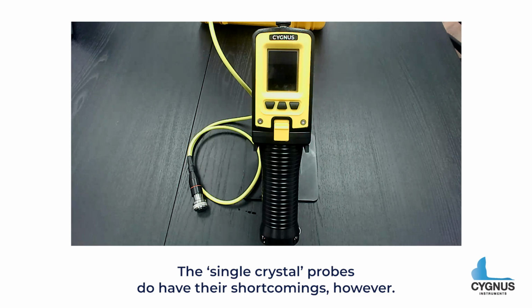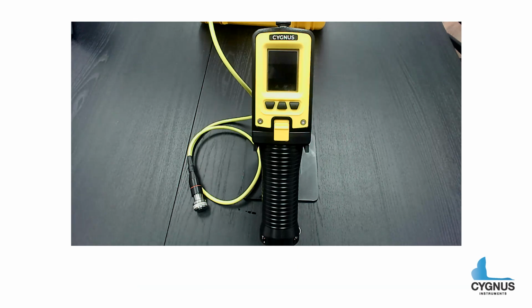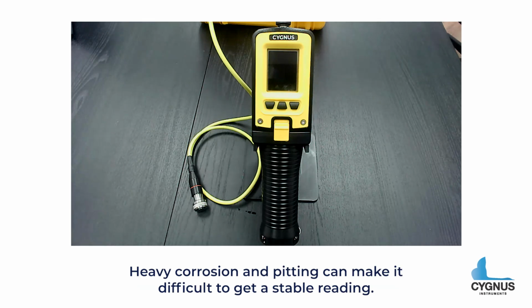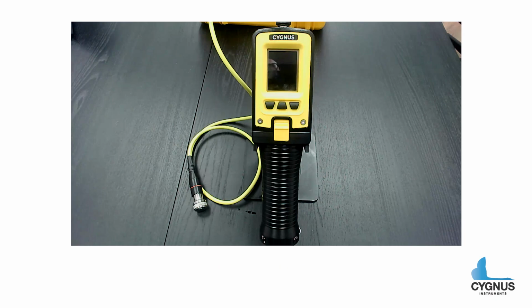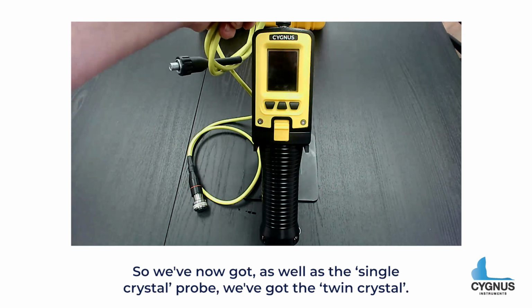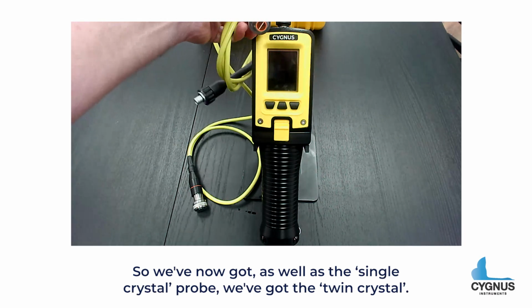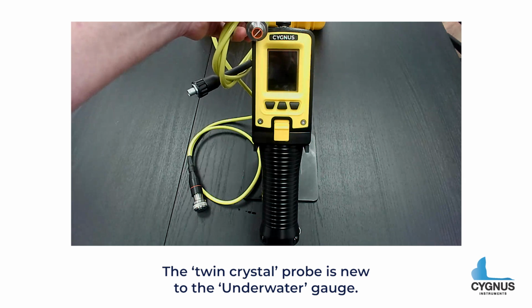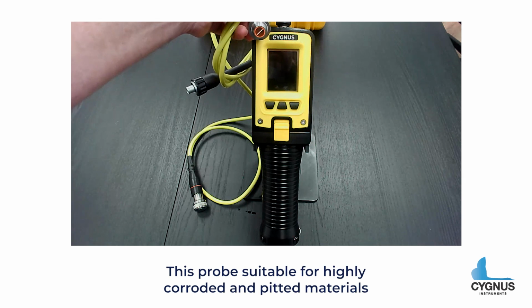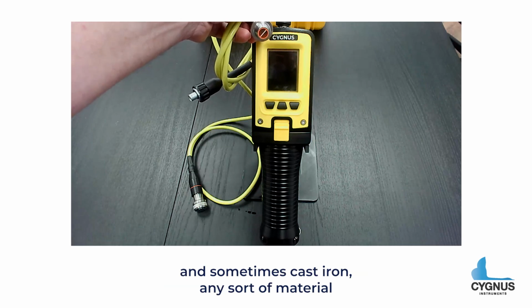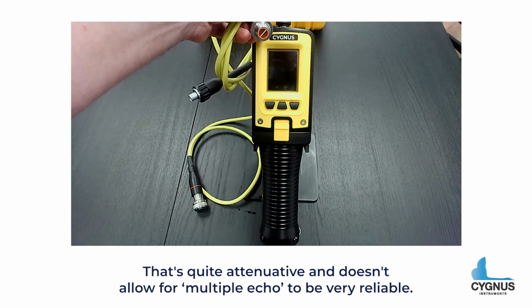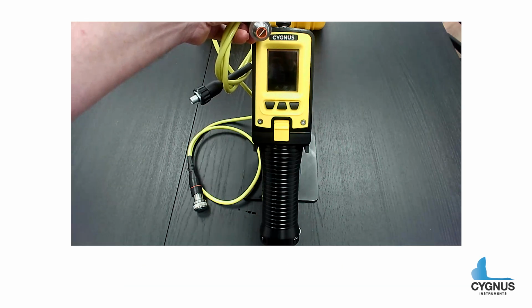The single crystal probes do have their shortcomings, however. Heavy corrosion and pitting can make it difficult to get a stable reading. So as well as the single crystal probe, we've now got the twin crystal. The twin crystal probe is new to the underwater gauge. This probe is suitable for highly corroded and pitted materials and sometimes cast iron, any sort of material that's quite attenuative and doesn't allow for multiple echo to be very reliable.